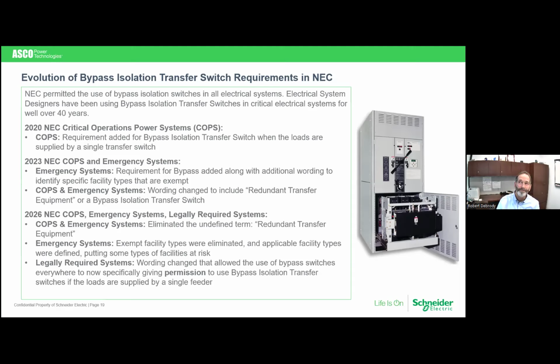And while they did that, they said, you know what, maybe we should change the wording. We don't want to isolate. The only way to get around that transfer switch is using a bypass isolation transfer switch. Maybe there's other ways. So let's put in the wording redundant transfer equipment. And they also said, well, we don't want to make this a burden on those facilities that they have to use a bypass switch in all cases. Let's say that if there's certain periods of time where that building is unoccupied and you can safely get around that transfer switch while it's being serviced, then it's not a problem. You don't have to implement this. So they put in some exceptions, which we'll go over in a slide or two later.